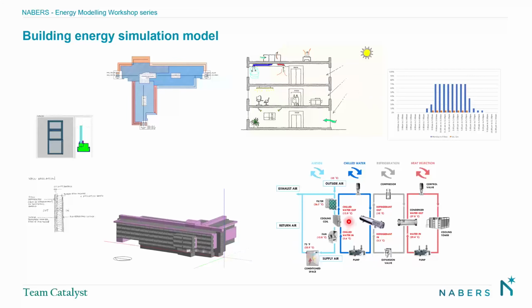That chilled water is generated by, in this case, a chiller. The chiller is represented by a compressor, a condenser vessel, an expansion valve, and an evaporator vessel. It all comes in one big piece. It provides chilled water, which is pumped around the circuit that cools this cooling coil.